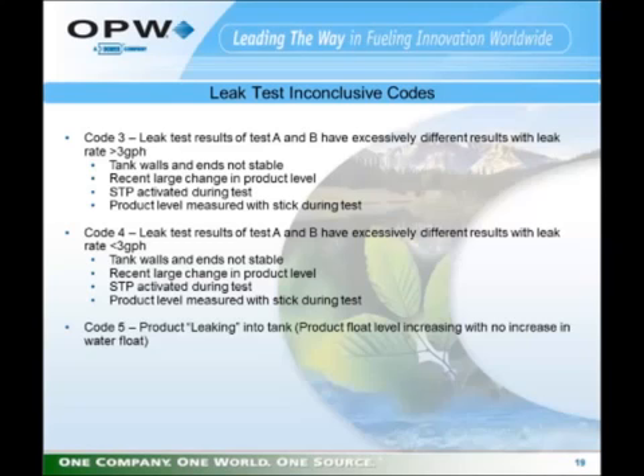And inconclusive code 4 is similar to the 3 with the exception that the leak rate indicated is less than 3 gallons per hour, but greater than allowed during the test. And again, the same conditions that would cause a code 3 can also cause a code 4.